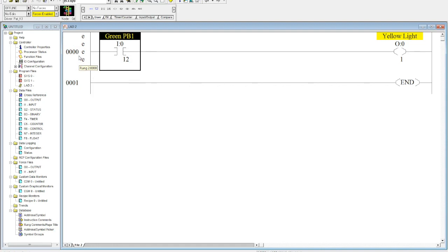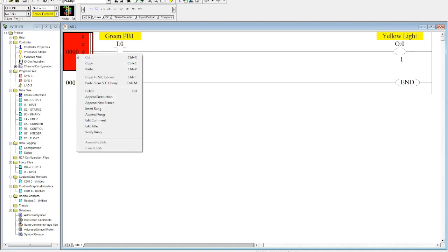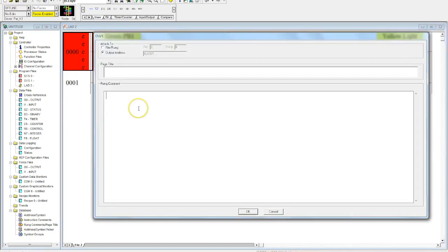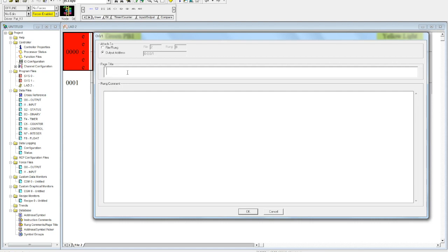Now if you want to add a rung description - and you typically should - this is how you do it. You right-click here and hit Edit Comment. Now there are some very important things you need to know before you do this. Be careful with your page title, because the problem is if you put your description in your page title, every single rung will be printed off on its own page.